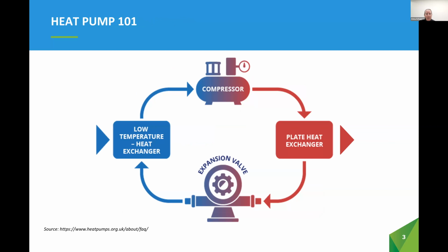Heat pumps, typically utilized in HVAC applications, use a vapor compression cycle. This is refrigerant circulated through 4 stages: expansion, evaporation, compression, and heat rejection. Air conditioners, chillers, and refrigerators use the vapor compression cycle for cooling, which is transferring heat from an inside space to an outdoor space. A heat pump uses the same cycle, but includes a reversing valve. The reversing valve allows the system to operate in 2 directions, either transferring heat from outside in or from inside out.